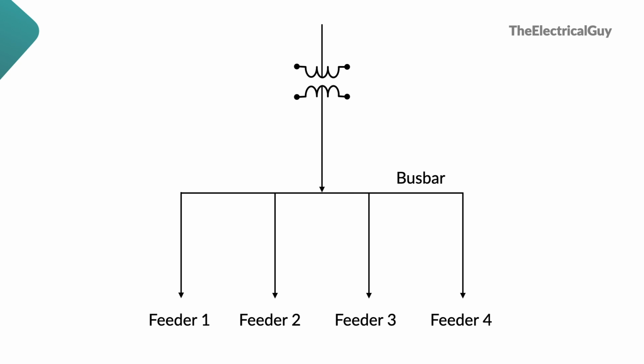A busbar in a substation usually energizes several feeders, which further deliver the power to different load centers or surrounding substations. The impedance of such a busbar is usually very low, and in case a short circuit happens on any feeder, the resulting short circuit current would be very dangerous. And hence it becomes very important to limit this dangerously high short circuit current in order to protect the system and equipment used in that system. And that's when current limiting reactors come into the picture.